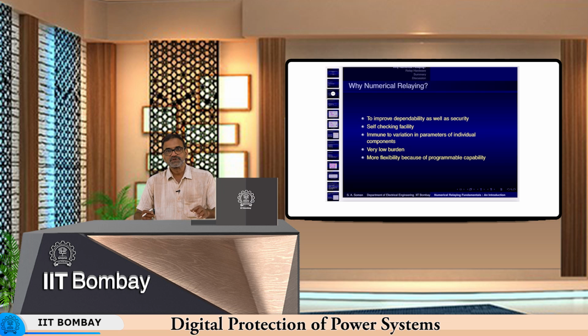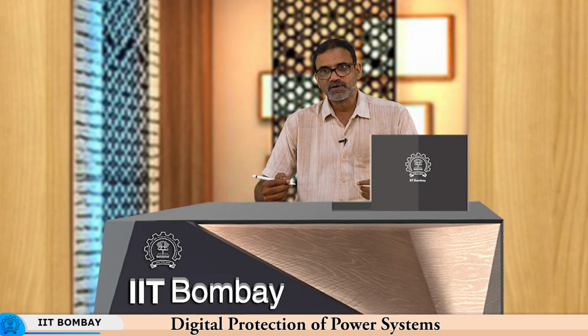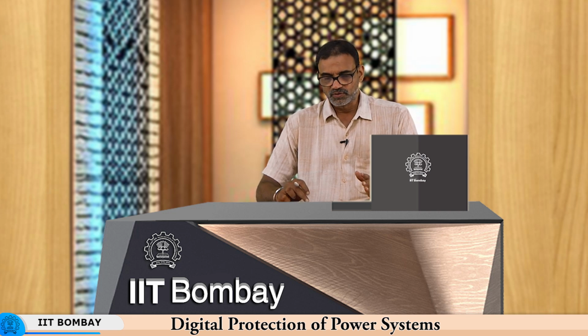One facility which was not there with electromechanical relays, but was there with static relays and is similarly present with numerical relays, is the self-checking facility. So, you can have a continuous check of whether all the parameters are okay, whether all the boards are working okay, whether the power supply is okay, etc., and give an alarm or a flag if it is not okay.